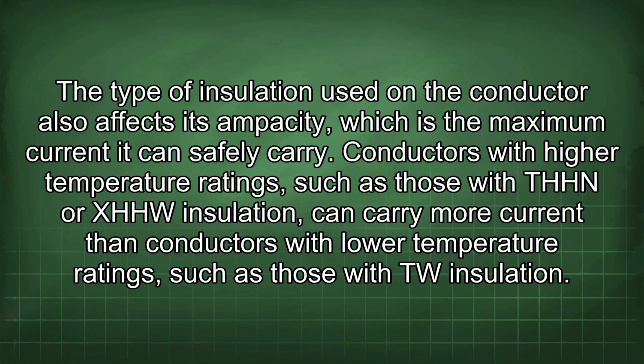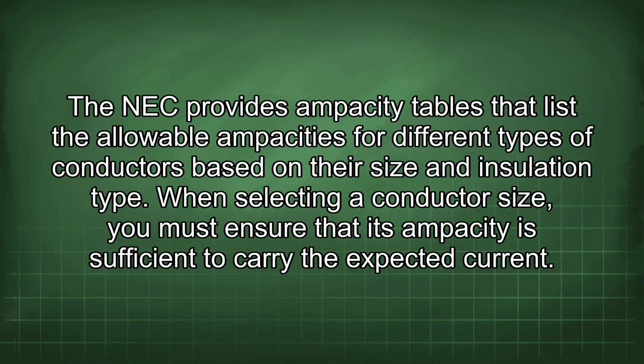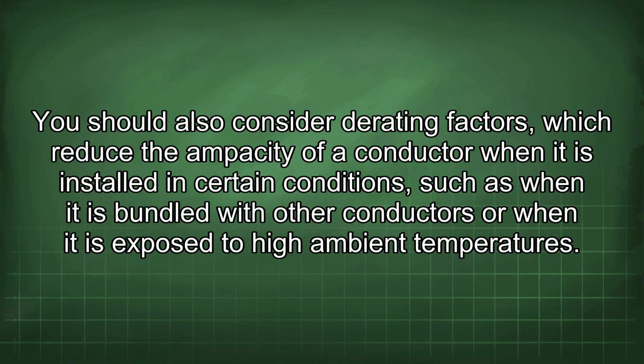The type of insulation used in the conductor also affects its ampacity, which is the maximum current it can safely carry. Conductors with higher temperature ratings, such as those with THHN or XHHW insulation, can carry more current than conductors with lower temperature ratings, such as those with TW insulation. The NEC provides ampacity tables that list the allowable ampacities for different types of conductors based on their size and insulation type. When selecting a conductor size, you must ensure that its ampacity is sufficient to carry the expected current. You should also consider derating factors, which reduce the ampacity of a conductor when it is installed in certain conditions, such as when it is bundled with other conductors or when it is exposed to high ambient temperatures.